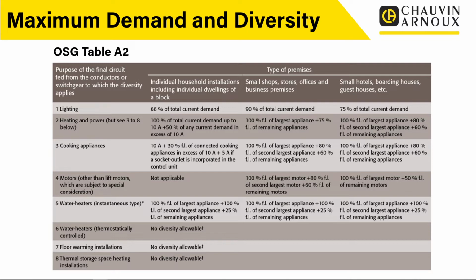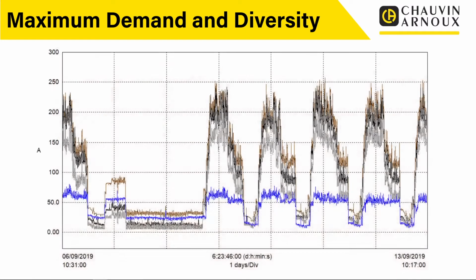So you're always better off, if you can, with actually measuring. If you have got an installation, or a very similar installation, where you're able to actually measure the maximum demand and see what it is, that's always a better way of doing it.